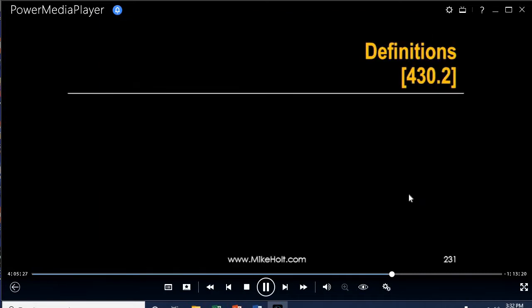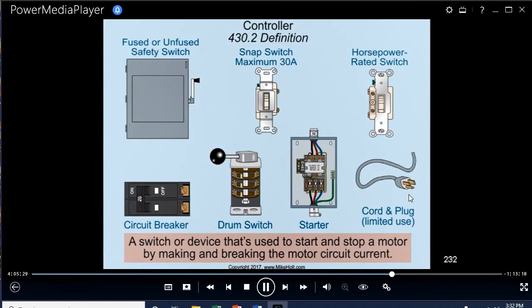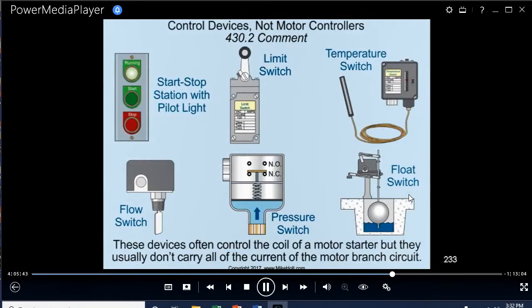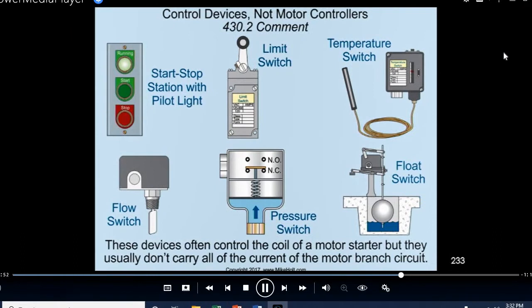The definition in 430.2: what is a controller? A switch or device that's used to start and stop a motor by making and breaking the motor circuit current. So all of these are ways to turn a motor on and off. And this is an example of devices that are not considered controllers. These devices often control the coil of a motor starter, but they usually don't carry all the current of the motor branch circuit. Let's see, the only one that could be, now this right here, no, this would be a controller.